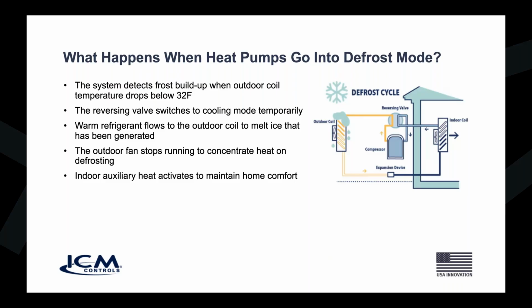All right, and so what happens there is now your outdoor coil is going to start warming up, melting any of that ice off, and then as soon as the sensor senses that the outdoor coil has reached, let's say, 55 degrees, it's going to say, okay, I've melted all the ice off, and tell the defrost board to switch the reversing valve again. The reversing valve is going to switch your refrigerant flow, and it's going to then go back to normal heating where the indoor coil gets hot and the outdoor coil gets cold. And this will keep repeating itself based on the defrost cycle and the intervals between defrost.